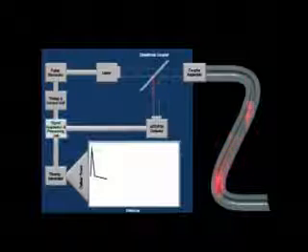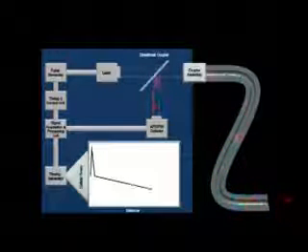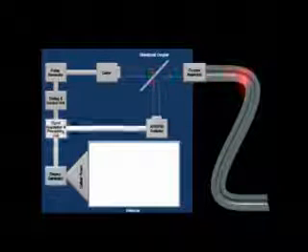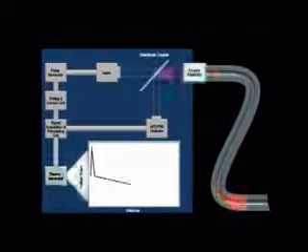The laser fires short, intense bursts of light that are directed through the coupler and then out through the front panel connector and into the fiber under test.